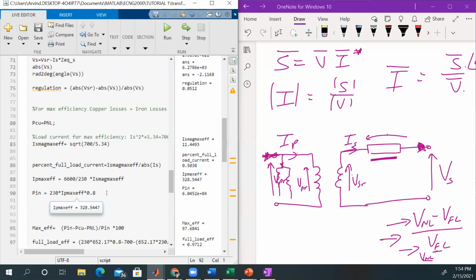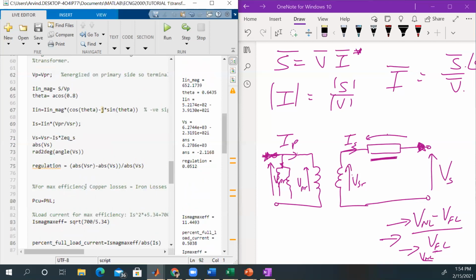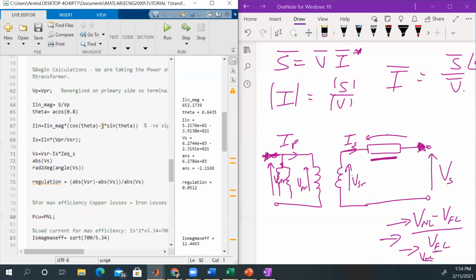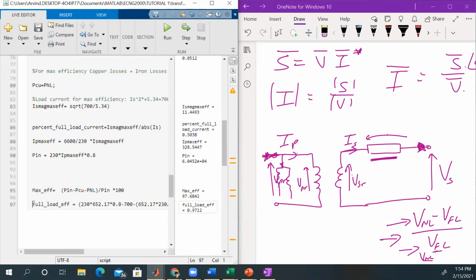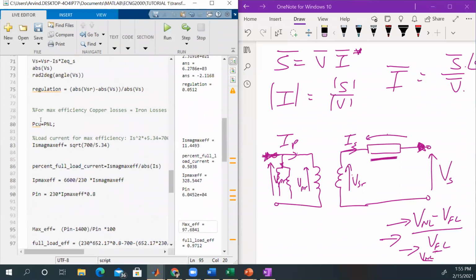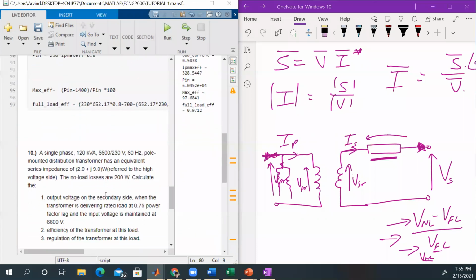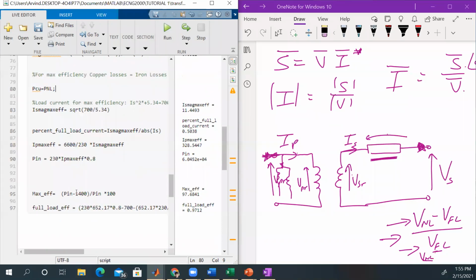Then you just do P out over P in, which is P in minus losses over P in. Let me check this, I think I have the wrong value here. P in, where did I get that from? P no load was 700 — this should actually be 1400 watts here, and you'll see it remains the same. Ah, PCU at no load — yes, you could take it as 1400, the same as PCU and PNL each set to 700 watts.